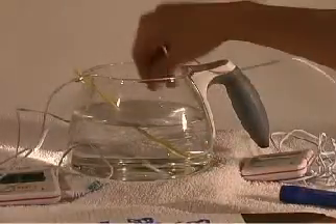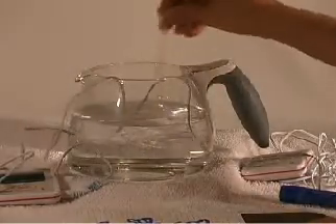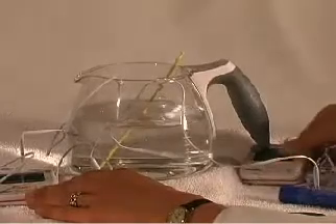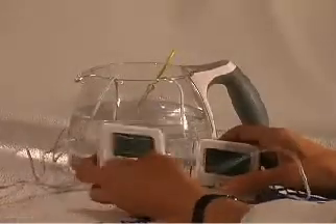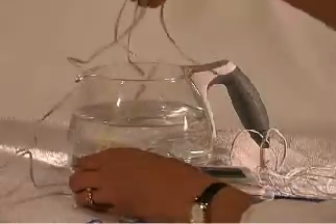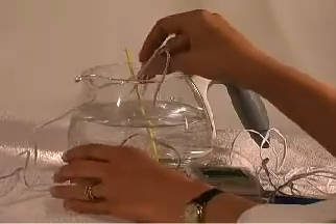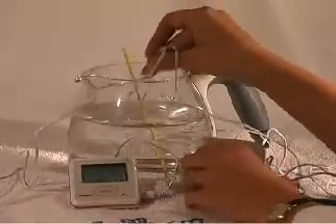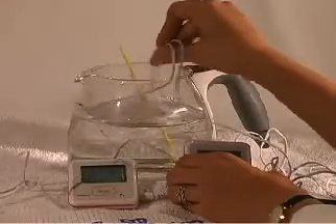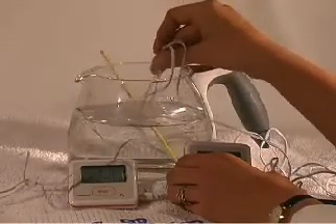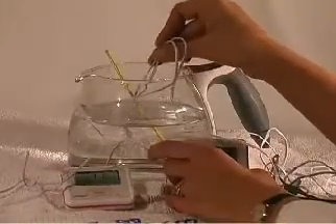Now we've got our ice melted, but it's still pretty cold. Let's take a look if we really stir it around and press the reset button on these and keep our probes really side by side. What do we get? Before anyone panics and invalidates data or recalibrates, it's always good to make another measurement. So we've got 11 degrees in A and 10 degrees in B.